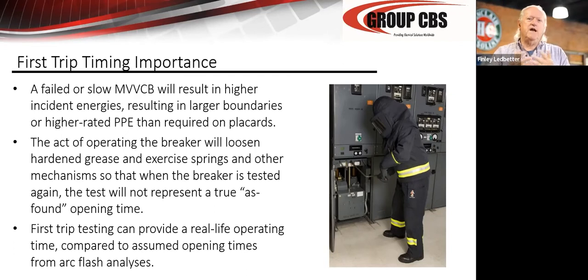So basically the time involved is mechanical time lost in opening the breaker. Then you have parting time. Then you have acceleration. Then you have stop and bounce. You have the time it takes to blow and extinguish the arc. And all of that has to operate in a symphony of times to make your arc flash study numbers correct. If any of that is too slow, your incident energy essentially is a factor of speed. So if the speed slows down by half, your energy really expands by a factor of two.